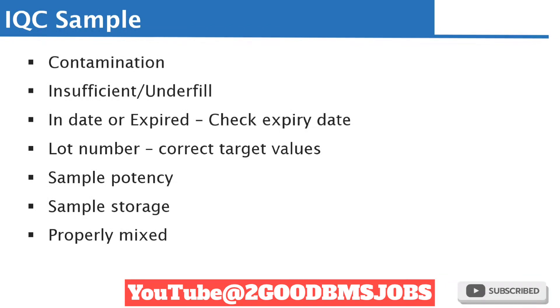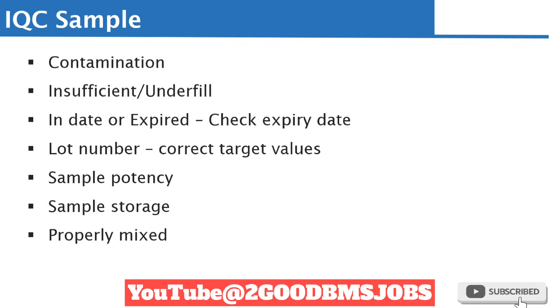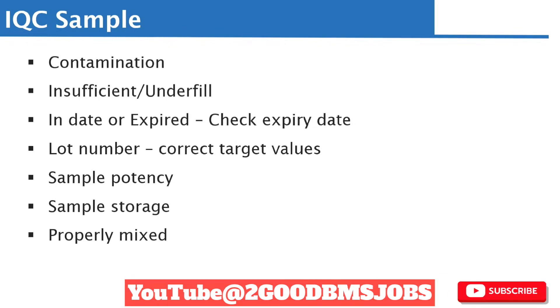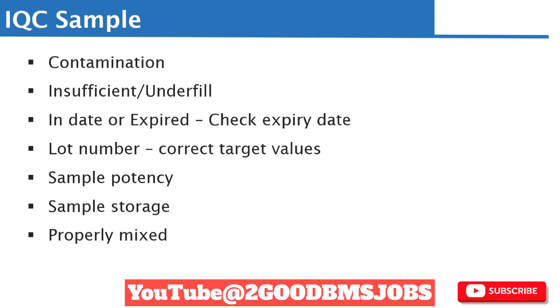Another thing to look at is the lot number of that control sample. Check whether it is appropriate — does the lot number correspond with the correct target value that is already inputted in the analyzer? If the lot number of the control sample is different from the target value on the analyzer, you need to get the appropriate lot number of control sample that corresponds with those target values.